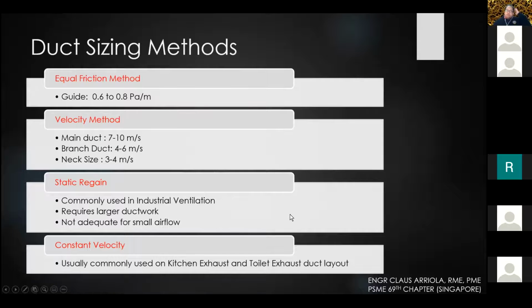Okay, so these are the following duct sizing methods. We have the equal friction method, which has a guide of 0.6 to 0.8 Pascal per meter. Then the velocity method, which is commonly used for engineered smoke control. Okay, because of the large volume of air in engineered smoke control, we normally use 7 to 10 meters per second, but usually it's around 10 meters per second to 12 maximum.